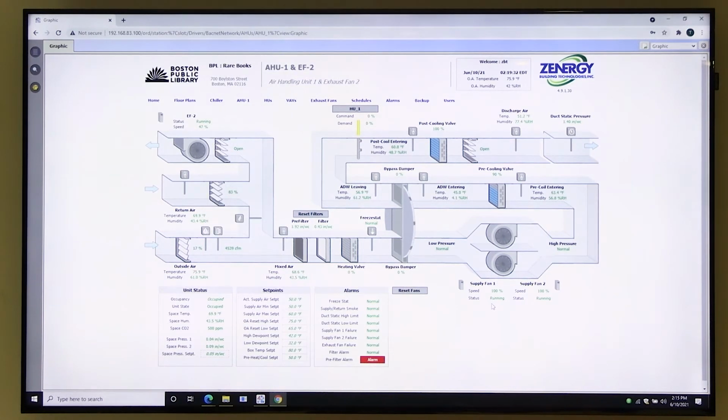So these little icons here are the VFDs. I think they have a runtime, but we don't have that built in for the air handler. Because with the water conditioning, we have to add salt, we do carbon filters, there's a lot of maintenance here, because we do not want to have to touch that heat wheel. Yeah, I get that. I just want an alarm that pops up and says whatever the manufacturer says to go in and do. So basically a runtime and a runtime alarm. Yeah, that's something we can do. That's not too difficult.